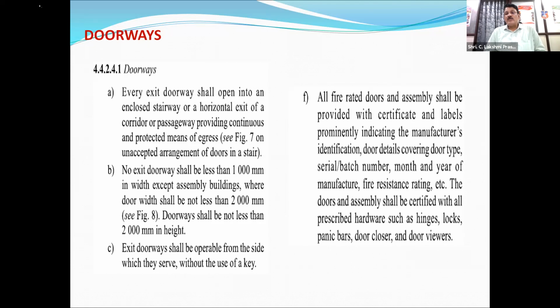And these doors should be normal. Any door for that matter will have 30 minutes fire resistance, even if it is a wooden door or metal door. So the fire resistance rating is required. Fire doors are required in the travel path at the exit. For all the staircases, the door has to be fire rated. Even if it is an internal staircase or external staircase, one has to go to the staircase through the fire door only, a 2-hour rated fire door. That is mandatory.